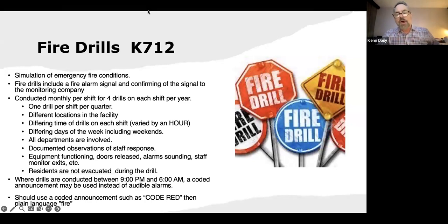And then, of course, making sure all departments are involved, making sure you're documenting your fire alarm. Again, you are permitted to use what's called a silent drill, meaning that if you don't want to pull the fire alarm in the middle of the night at 3 a.m. to do a third shift drill, you can do a coded announcement: code red, fire in the kitchen, staff please act accordingly. And then hopefully they would know to close doors, et cetera. And then the next morning you would test the fire alarm. Testing the fire alarm during a fire drill is really a separate test. That's actually an NFPA 72 test, in which we test the fire alarm monthly to make sure that the signal is being sent to the fire alarm monitoring company or fire department, whichever one yours goes to.